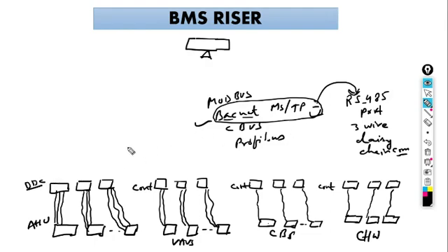You understand the difference between the protocol and topology. Okay, so suppose these DDCs are going to be connected with BACnet over MS over TP. In these controllers, they have a port with 3 connections, because we are going to use this 3-wire port. This is called the RS485 port. Even here, 3-wire connection. This is called the RS485 port. You can take a controller and look into it. This is called the RS485 port.